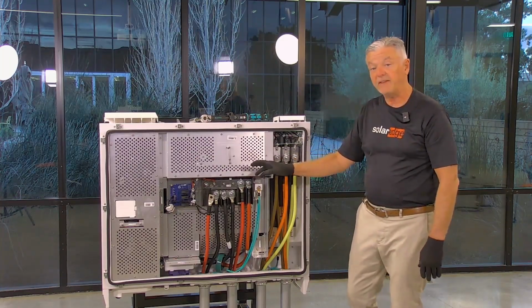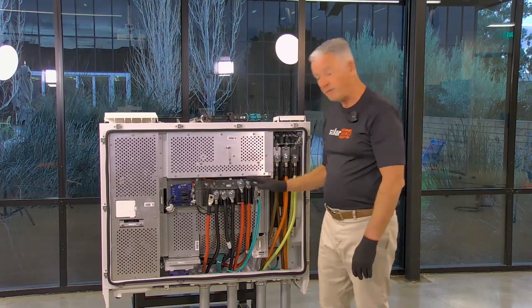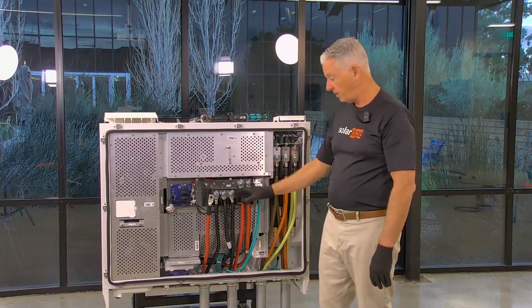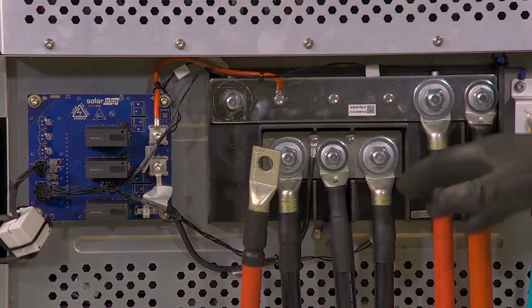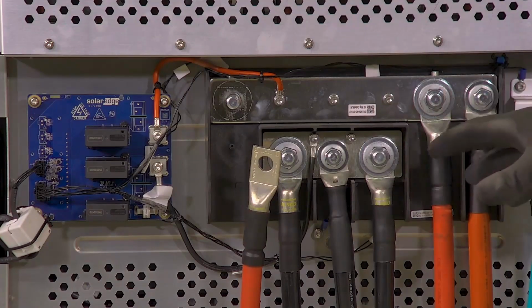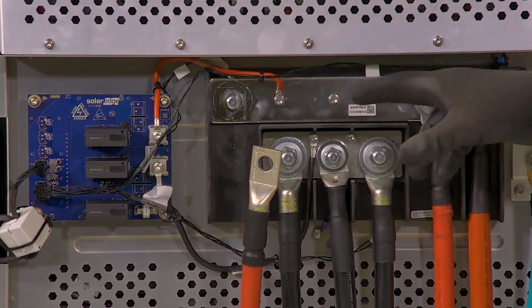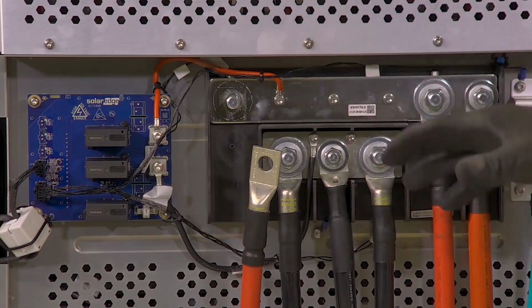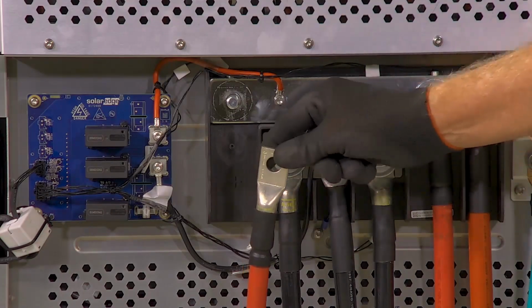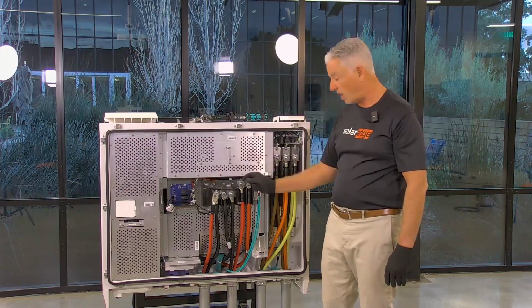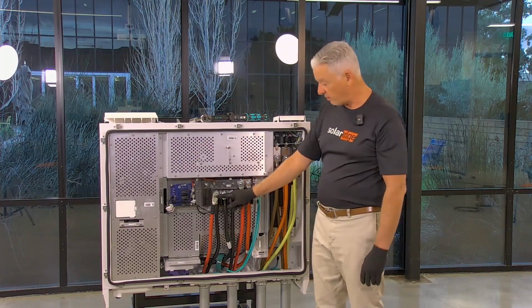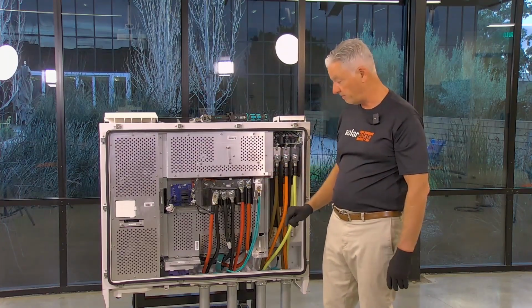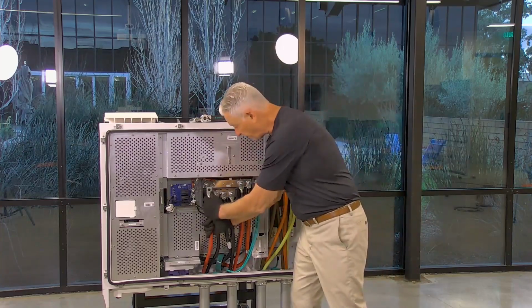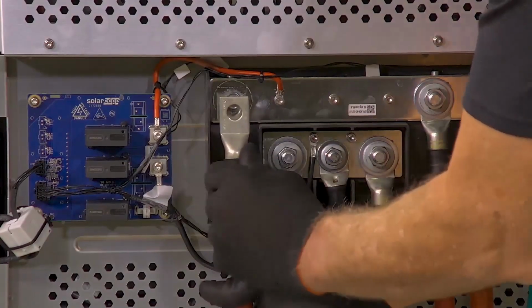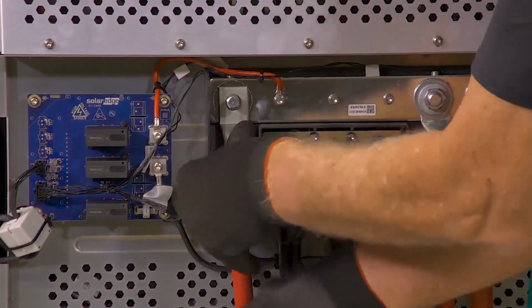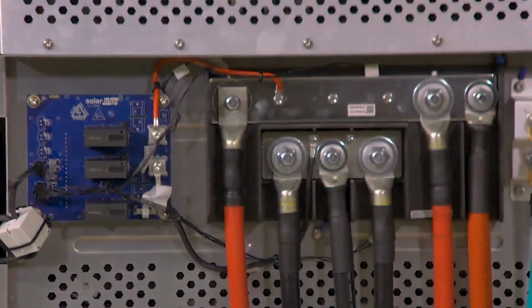We're going to do the same thing on the DC side now. Same specifications for the conductors, for the compression lugs, up to 600 kcmil conductors on both terminals. It can be copper or aluminum. The compression lug again can be at the most 1.77 inches wide, ½ inch thick, and with a ½ inch bolt hole. You seat the conductor with its compression lug on the threaded stud, and you seat it on the terminal block.